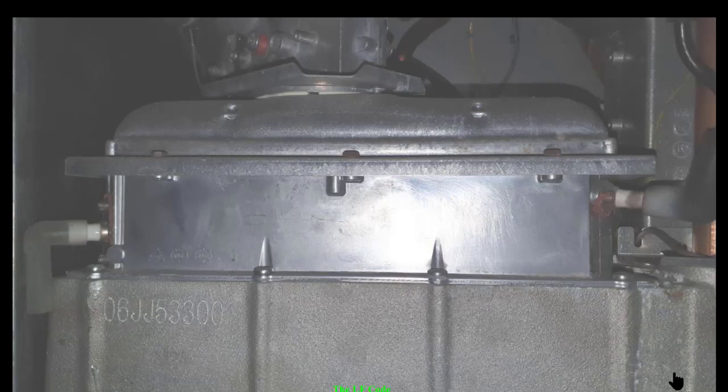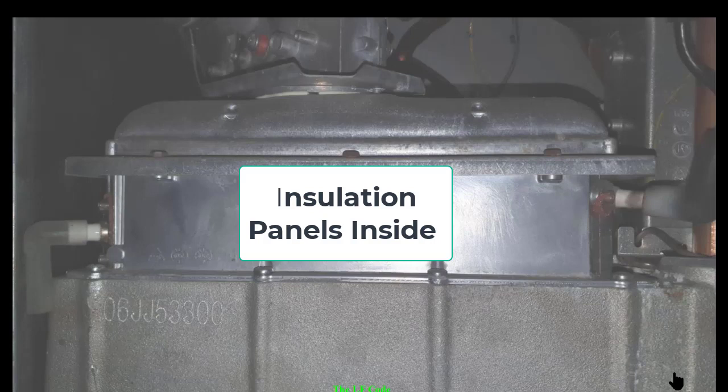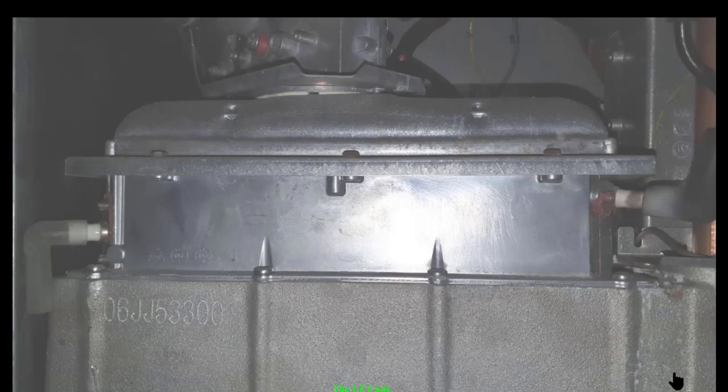Inside the heat exchanger, just above where the burner is, you've got insulation panels. What can happen is the insulation panels can fall down onto the flame detection probe, and so when it goes to ignite, the flame detection probe cannot see the burner flame, and then it will give you no detection and throw that fault. That's very highly unlikely. But when we go through all the checks we're going to go through now, if they're all good and there are no problems in those areas, then that's what you'll be looking at as your last resort.